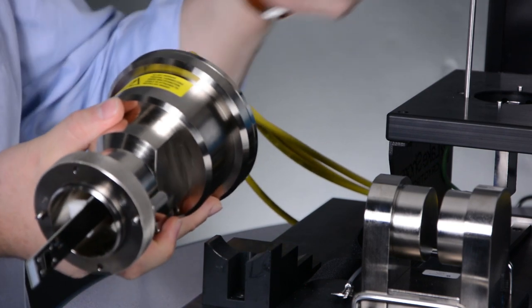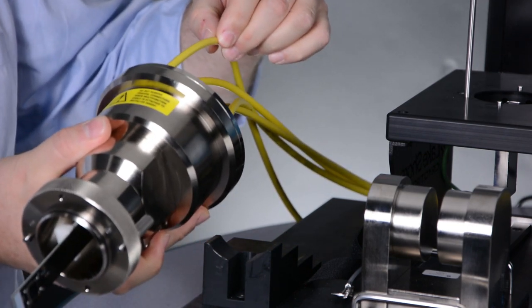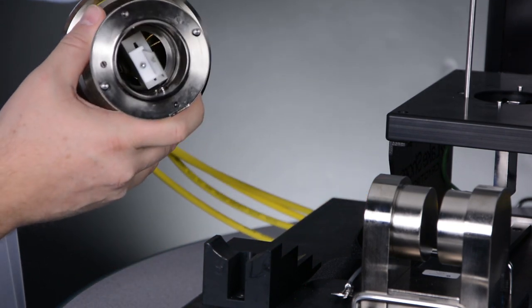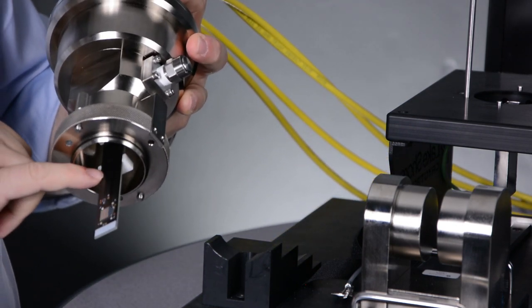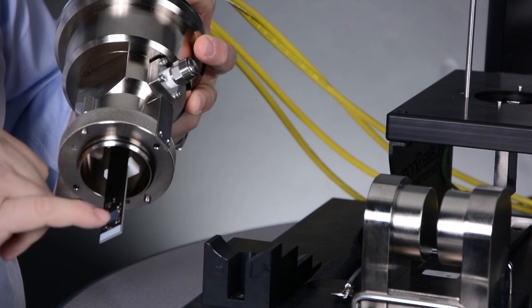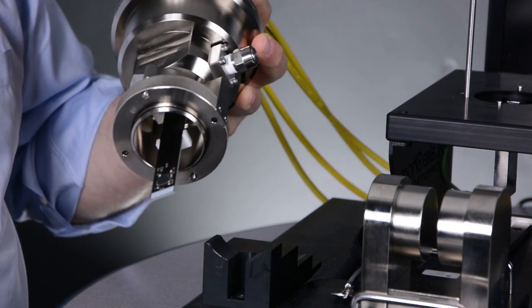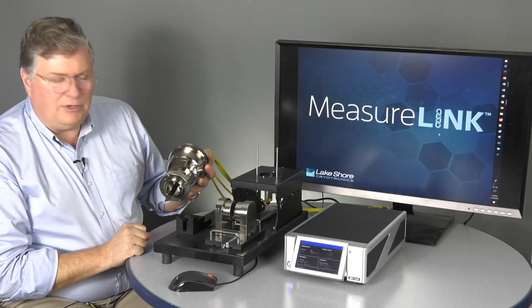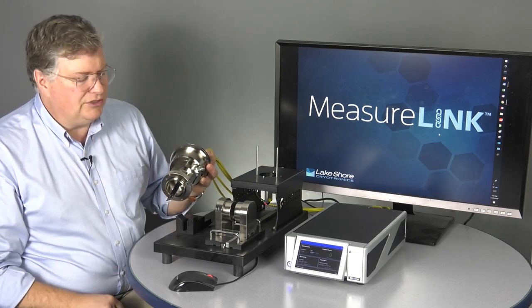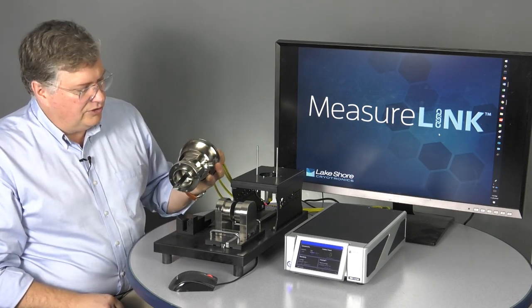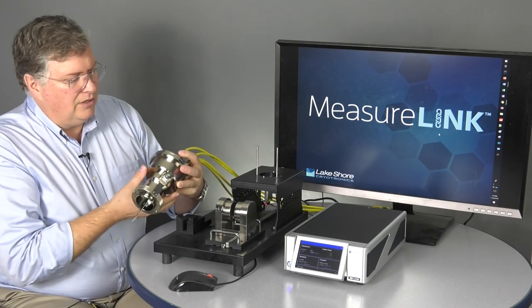We also have guarded Tri-Ax connections coming in from the M91-HR. Those guards are maintained all the way through our sample holder, and in fact, all the way as much as possible down through our sample card directly to the connections. So, we'll get into the sample cards in a minute, but we do have soldered and probed versions of these cards, and we'll go through a little bit of that in the demo here.